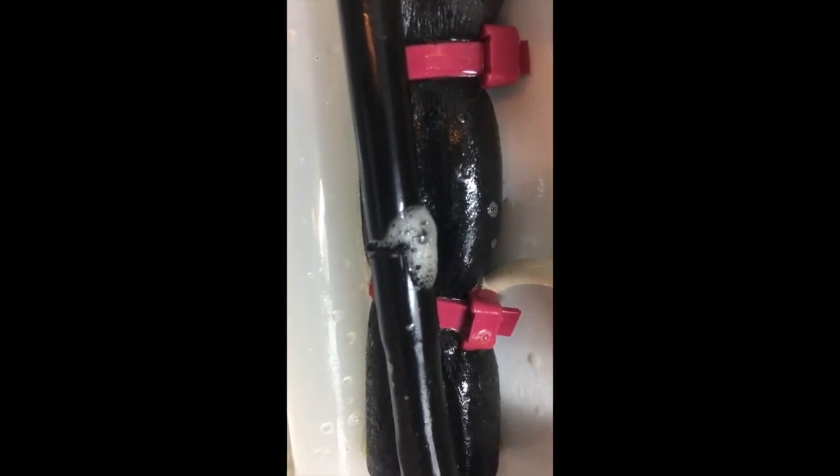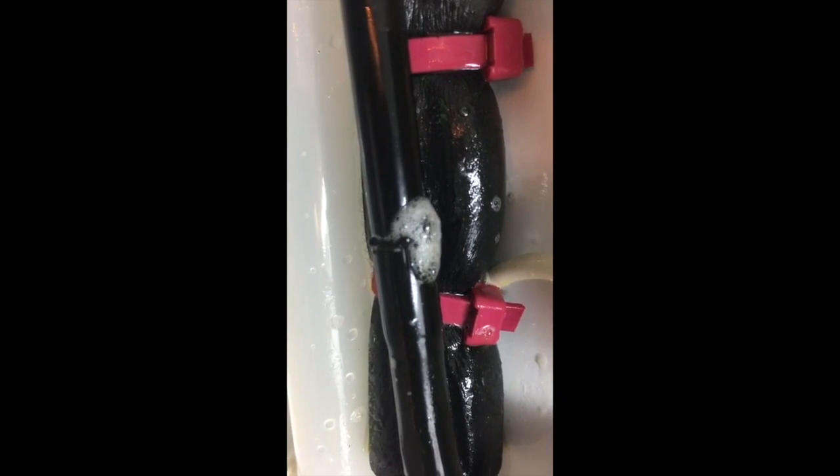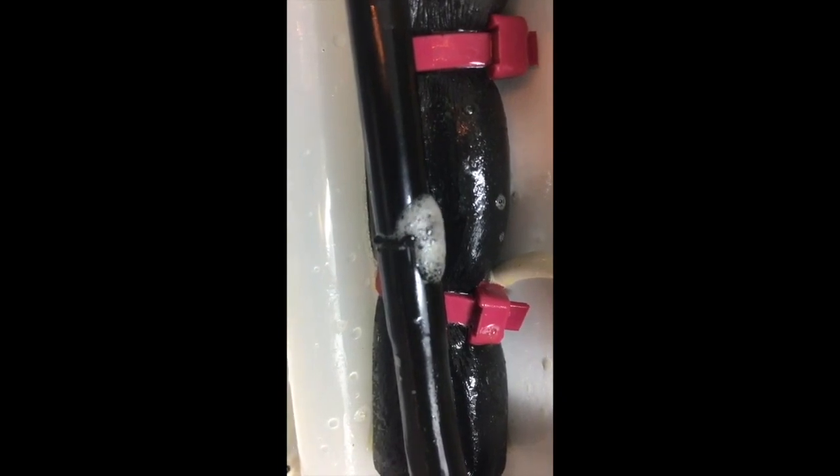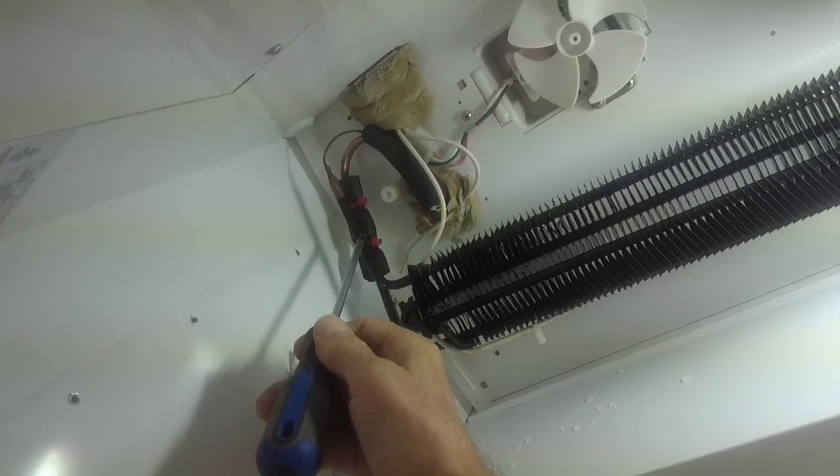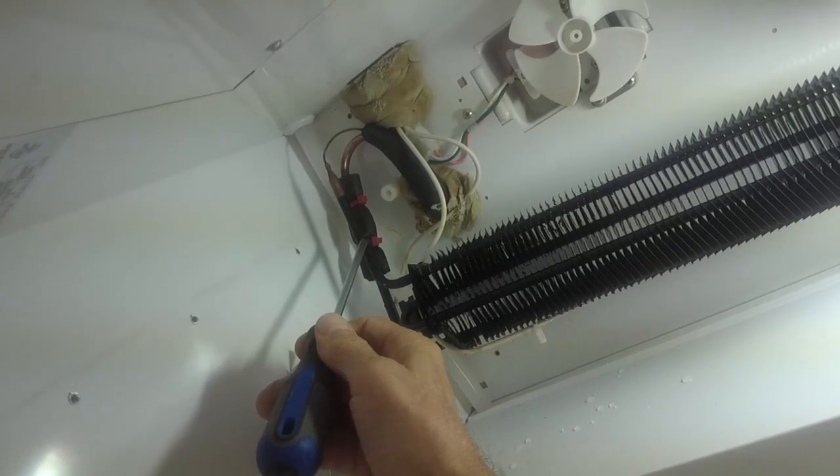Now I couldn't pick this up with a halide leak detector, but you can see it's the braze joint. So now you know, right there.